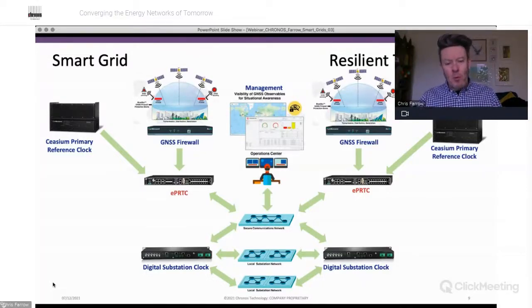We're seeing more awareness of security and cybersecurity vulnerabilities in these networks, so operators are bringing that timescale under their own control using local atomic clocks like cesium. When the GNSS signal is good, they steer these local cesium clocks towards UTC, so that if interference occurs with the satellite signal, the local timescale owned by the power utility company can hold accuracy to UTC for less than 100 nanoseconds for many weeks. This gives us the concept of an enhanced primary reference time clock, providing a clock reference for the whole network, not just the telecom network.